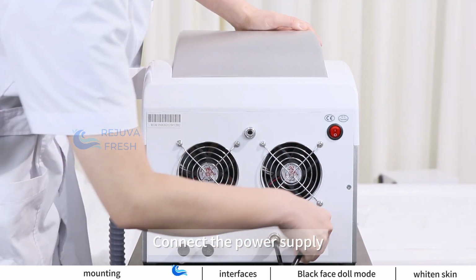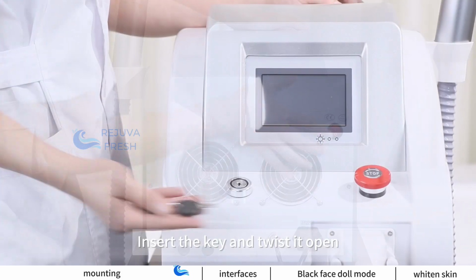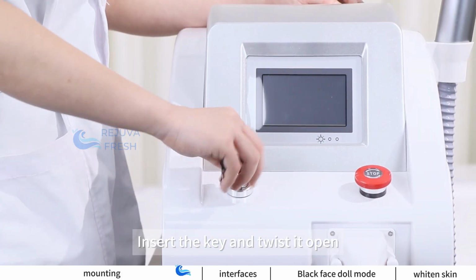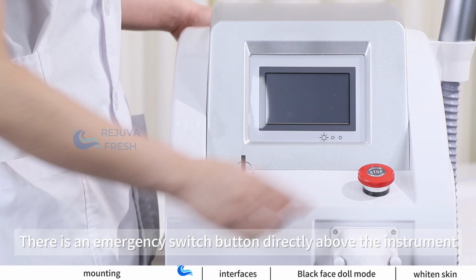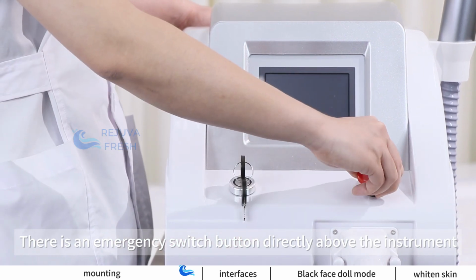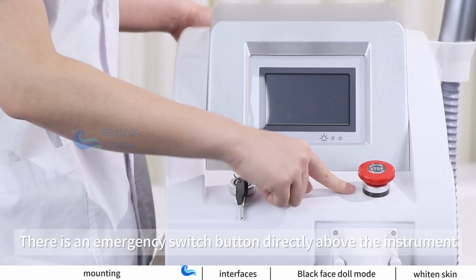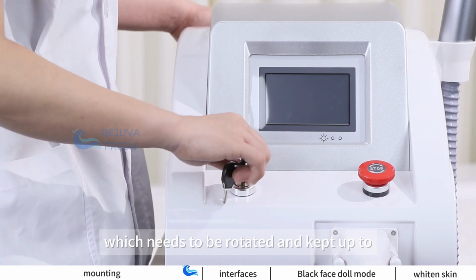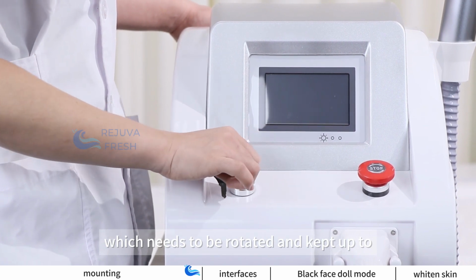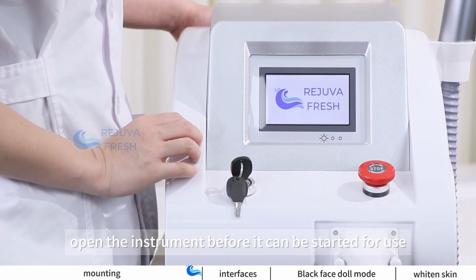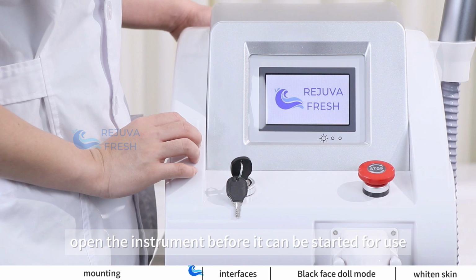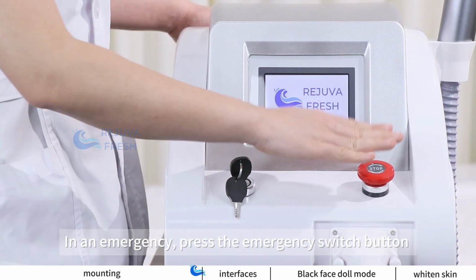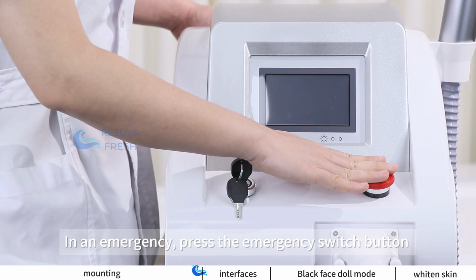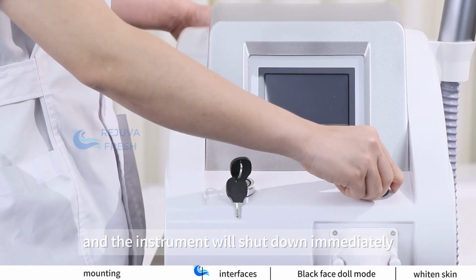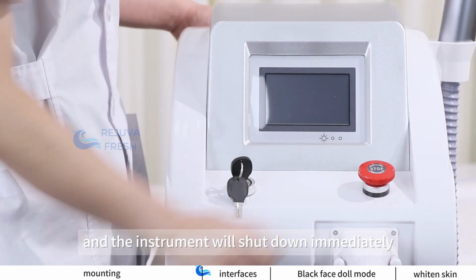Connect the power supply. Insert the key and twist it open. There is an emergency switch button directly above the instrument, which needs to be rotated and kept up to open the instrument before it can be started for use. In an emergency, press the emergency switch button, and the instrument will shut down immediately.